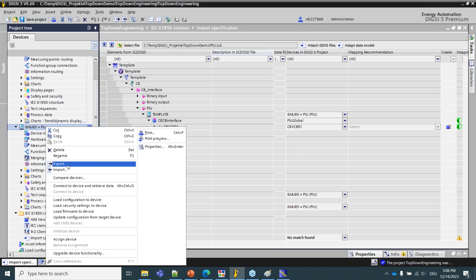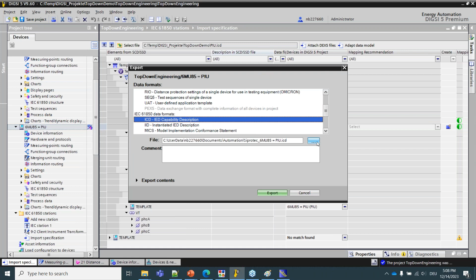This is what I will do now, import the data model, and we will see that the merging unit device now contains exactly the names as required. The circuit breaker is called CBXCBR1. The LTMS1 was called LTMS0 by default, has been changed, therefore reducing or avoiding as much as possible the deviations from the specified data model. So now that the device is exactly or as close as possible to the specification, I export the ICD file again as a process ICD, and I hand that over to the next step of the application.